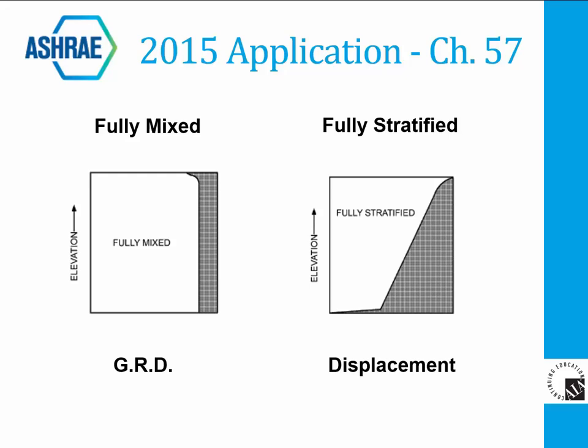As shown with the diagram on the left, space temperatures from the floor level to the return level have very little stratification. By design, displacement outlets are located near the floor with cool air introduced at low velocities, usually less than 100 feet per minute. Slight mixing occurs near the floor until heat sources in the space cause air to stratify, resulting in temperature increases in the space from the floor to the return height.